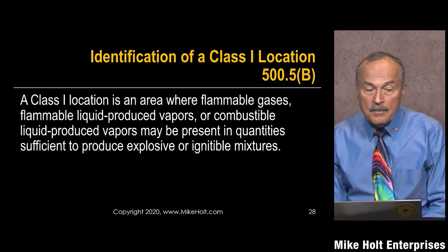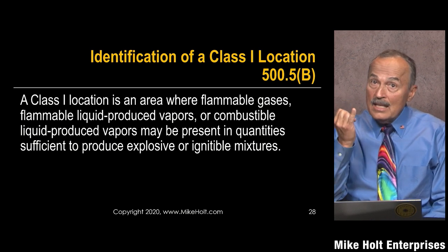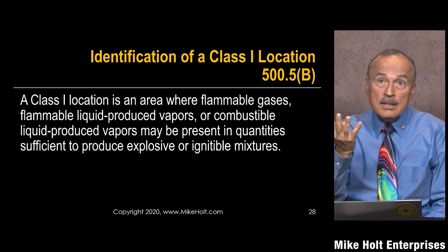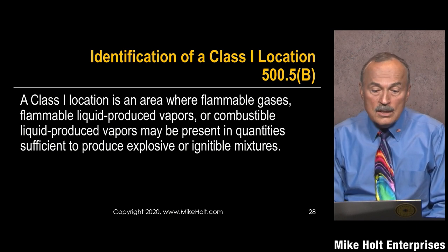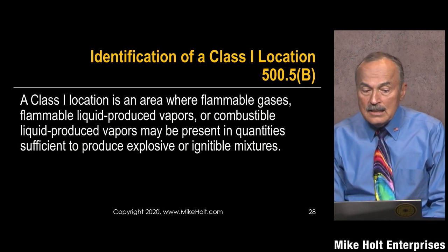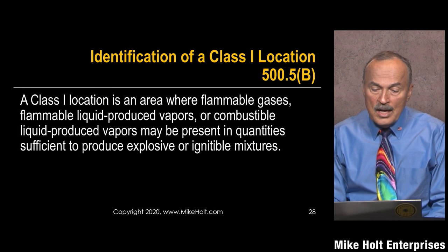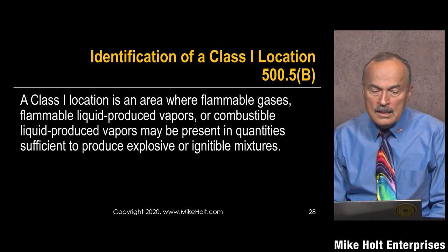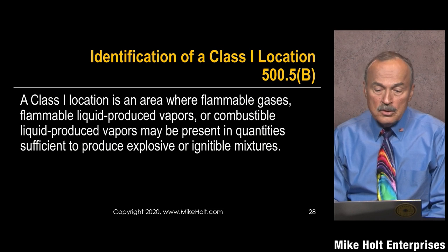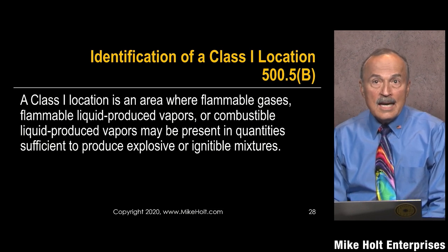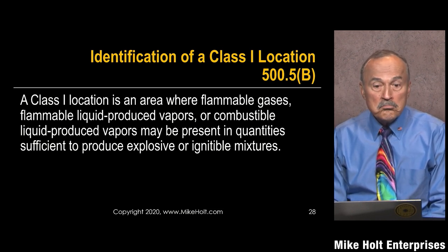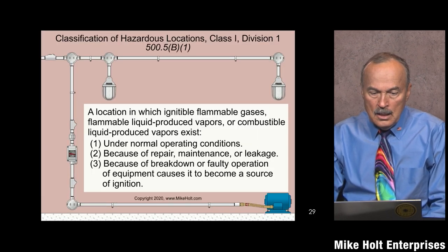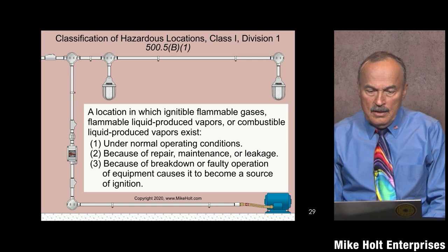In a Class 1 location — and we're going to cover Class 2 and Class 3 as well — Class 1 is a location where flammable gases, flammable liquid-produced vapors, or combustible liquid-produced vapors may be present in quantities sufficient to produce an explosive or ignitable mixture.